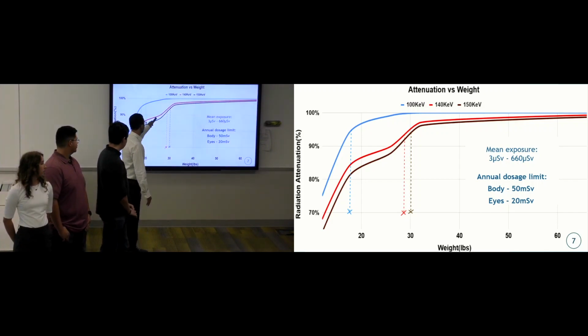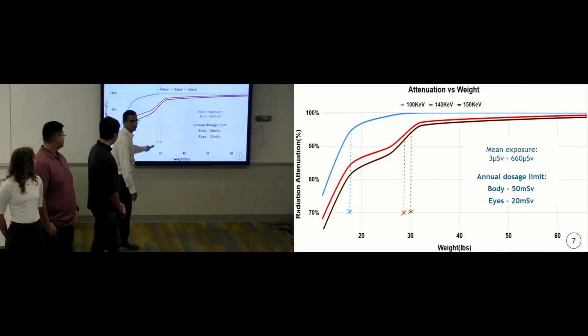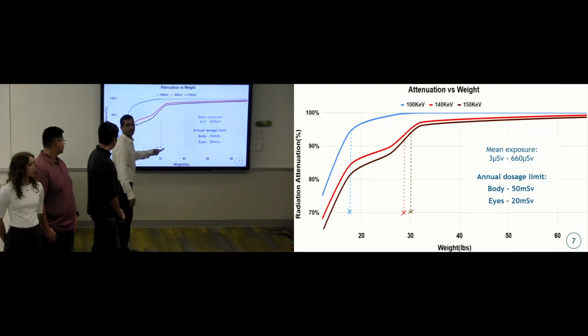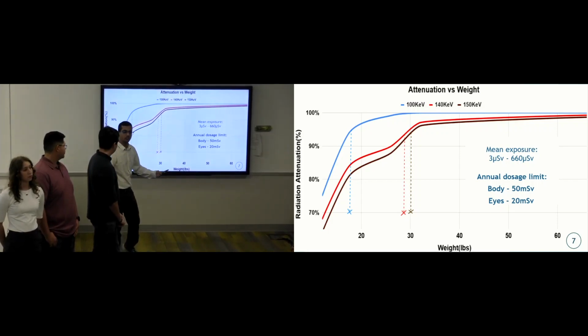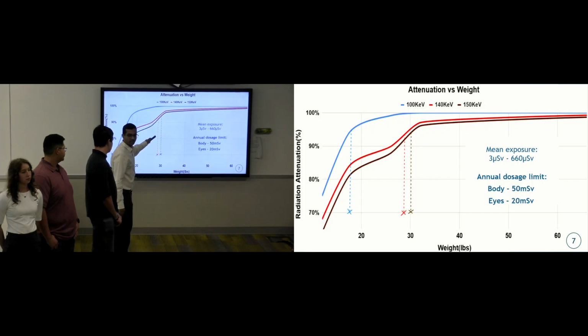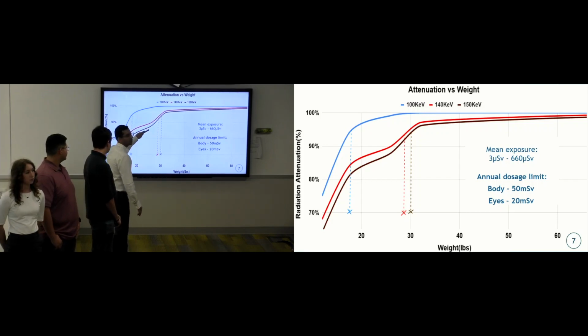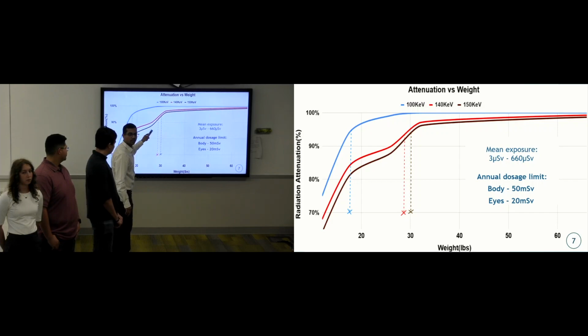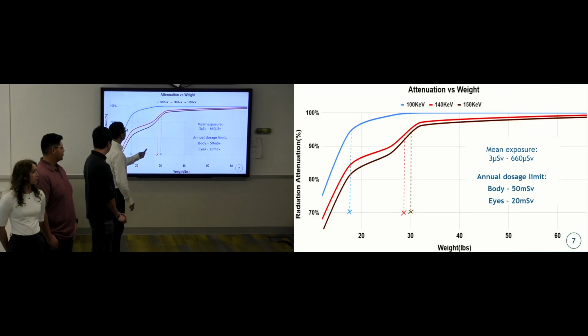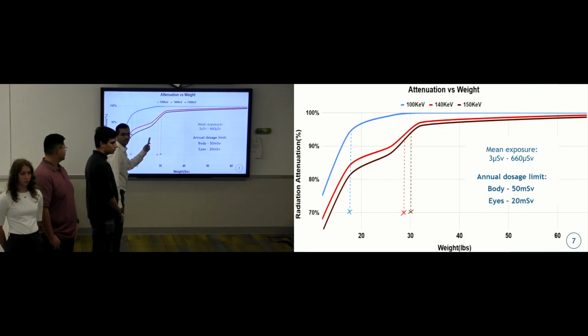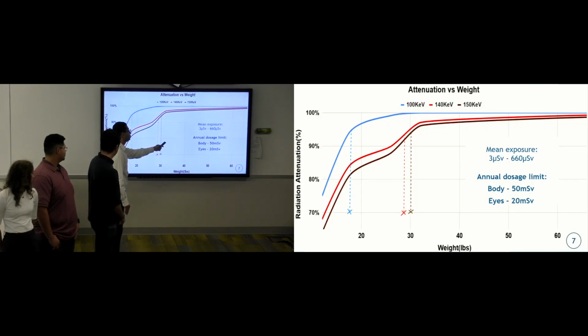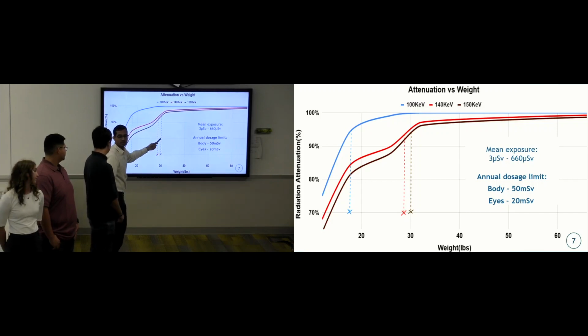So we can see that our optimal weight comes around 26 to 30 pounds. And since the weight of the shield is directly proportional to the lead equivalency thickness, we have an estimate of around 0.8 to 1.2 millimeters of lead equivalency thickness, and that's why we chose 1 mm. Also, the International Commission on Radiological Protection guides that the annual dose limit for an operator is 50 millisieverts for the body, and for the eyes it should be 20 mSv, so as to avoid cataracts.